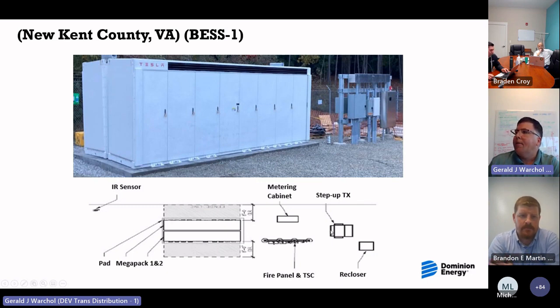We leave the metering cabinet and then come to a step-up transformer. The low side of that step-up transformer is 480 volts AC. We step that up to 34,500 volts. We go out through a recloser, which is a fancy distribution term for a circuit breaker, and then we go out onto the system.